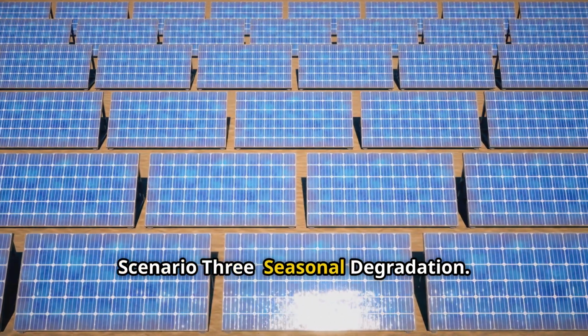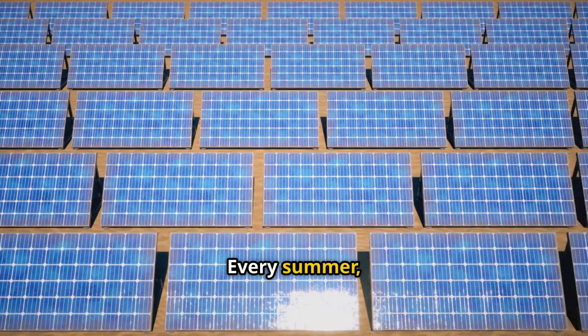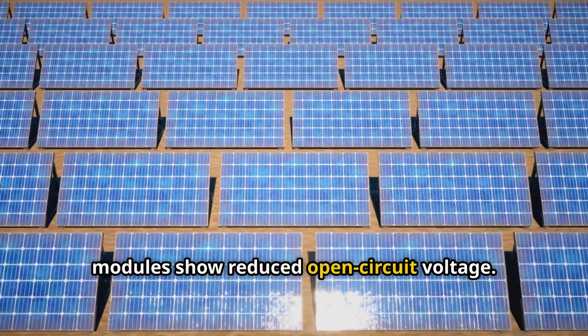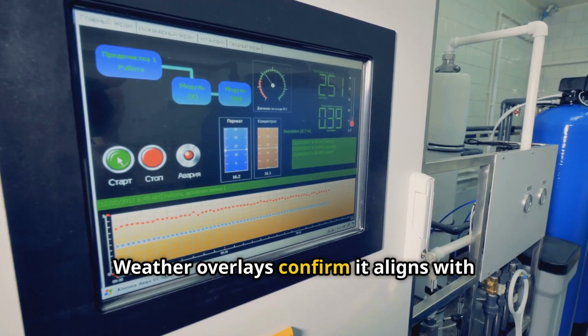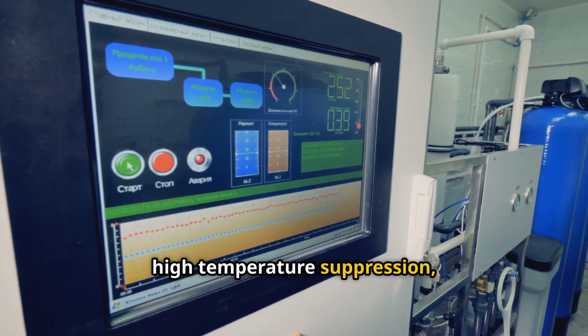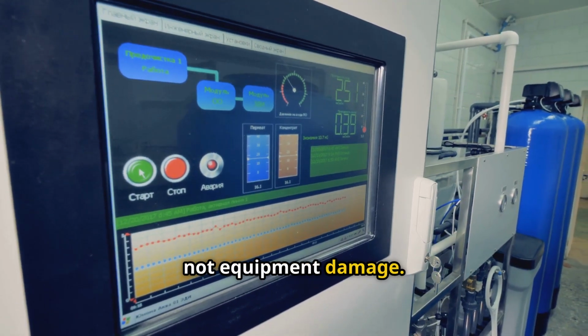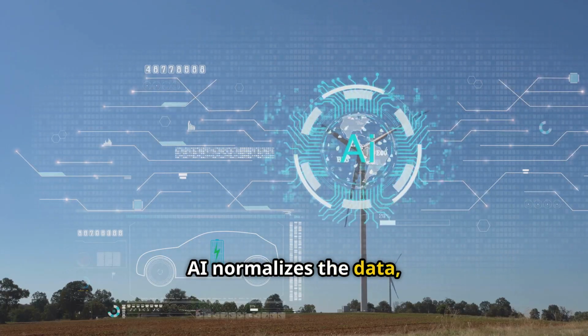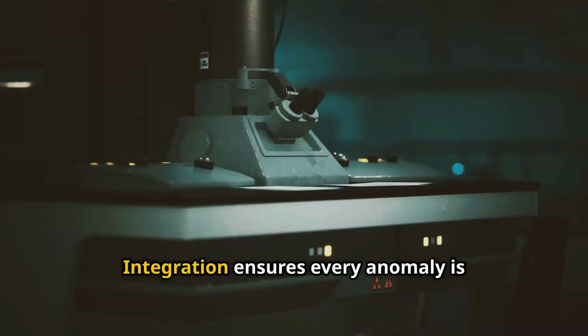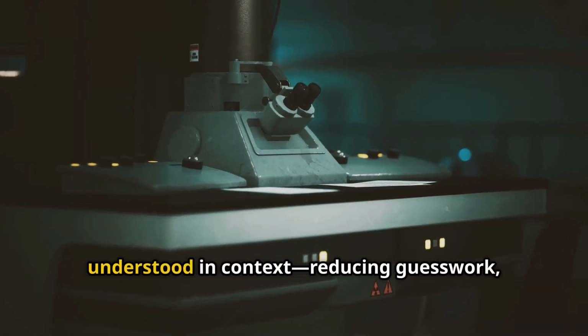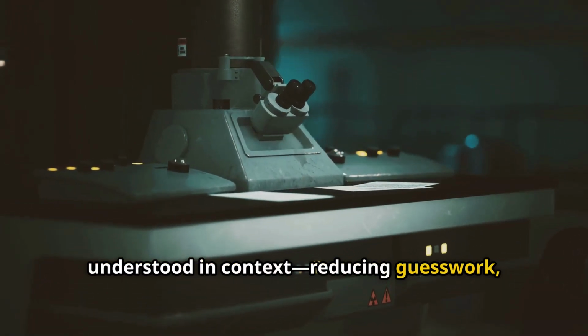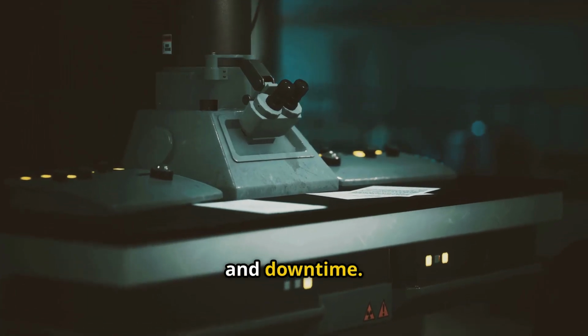Scenario 3. Seasonal degradation. Every summer, modules show reduced open-circuit voltage. Weather overlays confirm it aligns with high-temperature suppression, not equipment damage. AI normalizes the data, avoiding misdiagnosis. Integration ensures every anomaly is understood in context, reducing guesswork, wasted maintenance, and downtime.